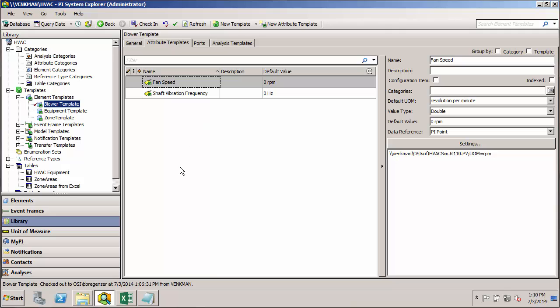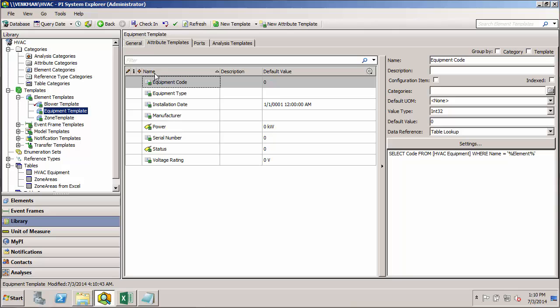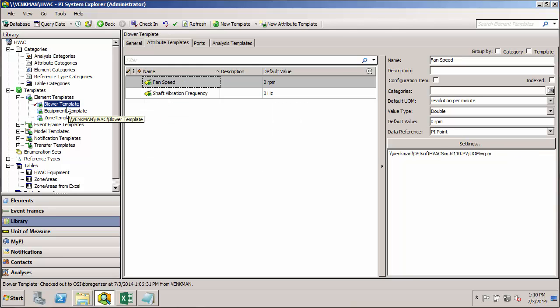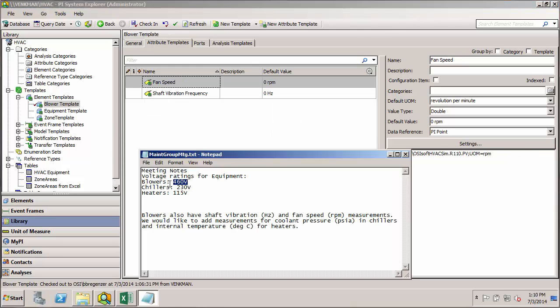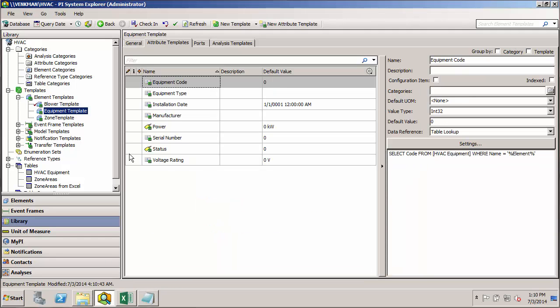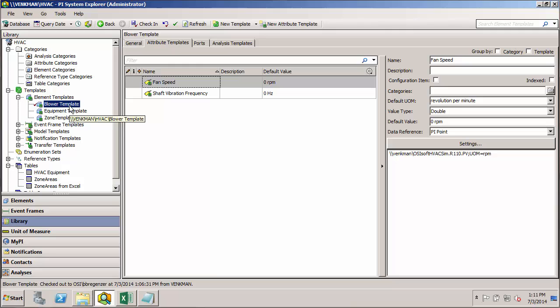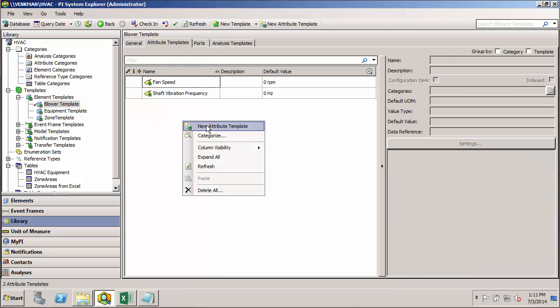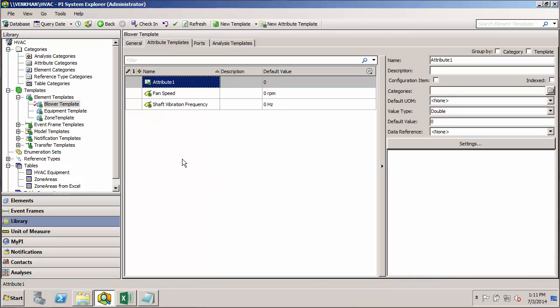In this case, our blower template would normally inherit all the same attributes from the parent equipment template. But maybe we don't want to use the value or the configuration string that's given by this template. Because we know that each class of equipment has its own unique voltage rating. So rather than having to go in and type in 460 for every blower element and 230 for every chiller element and so on, what if we just built that default value into the equipment specific template and then had that override whatever value is given by the base template.